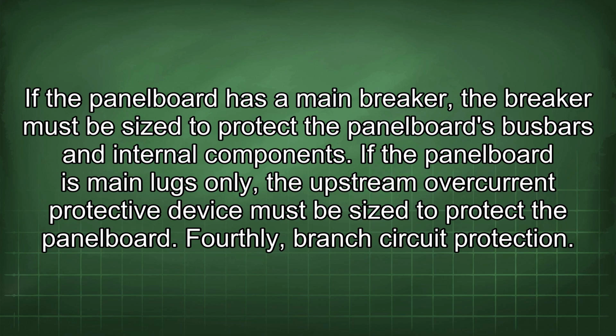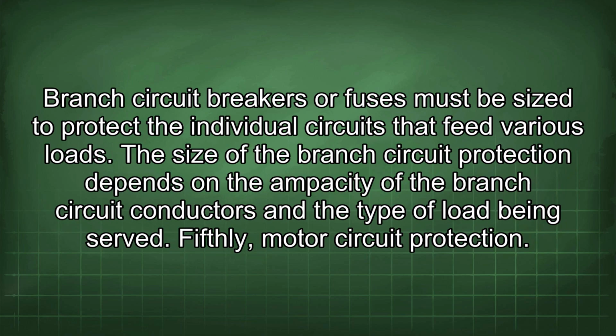If the panel board has a main breaker, the breaker must be sized to protect the panel board's busbars and internal components. If the panel board is main lugs only, the upstream overcurrent protective device must be sized to protect the panel board. Fourthly, branch circuit protection. Branch circuit breakers or fuses must be sized to protect the individual circuits that feed various loads.